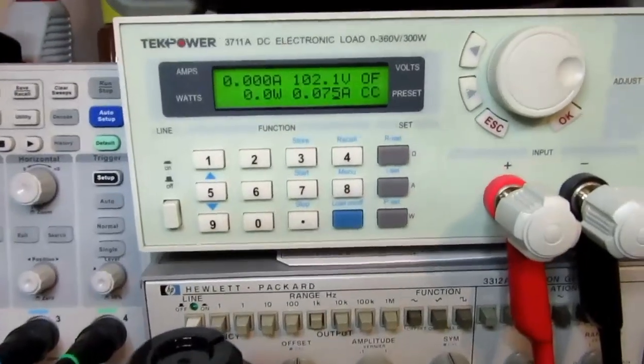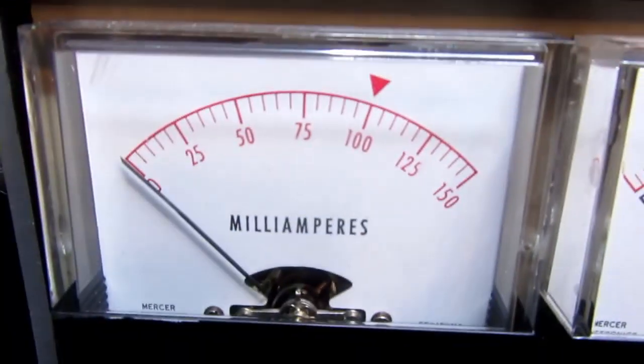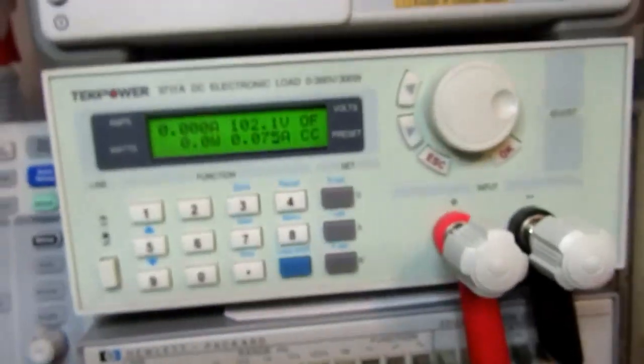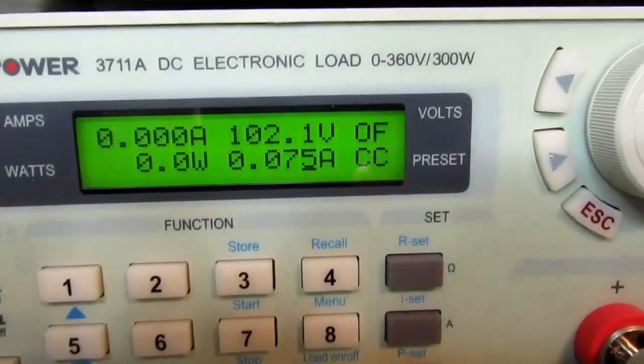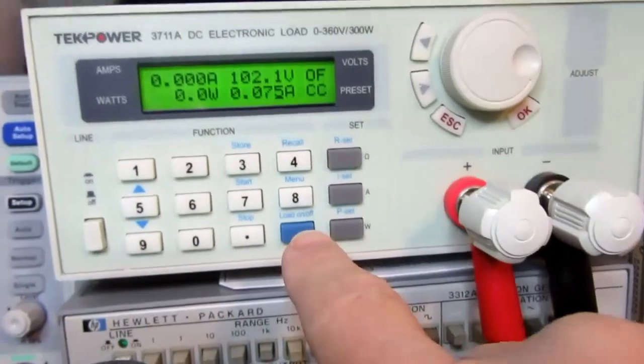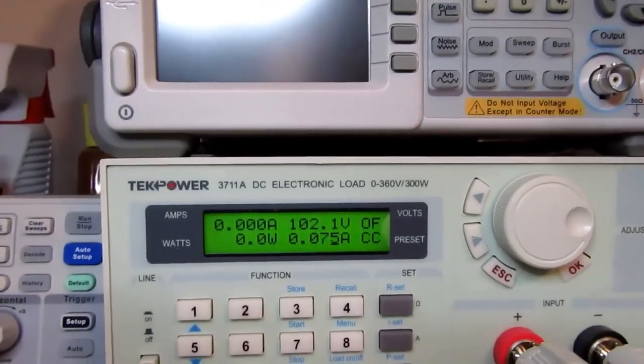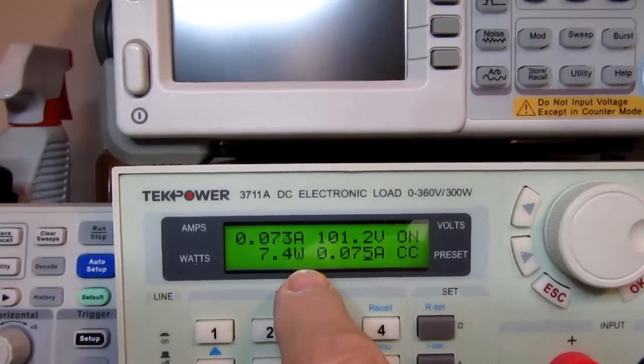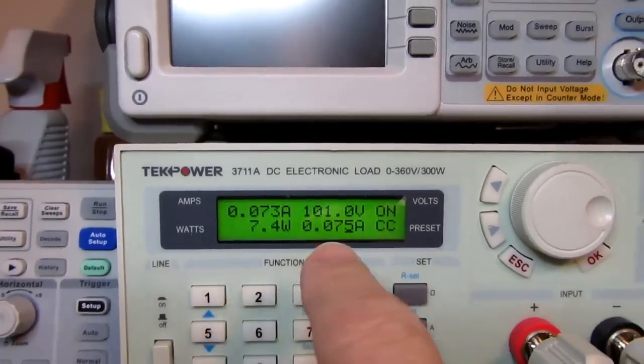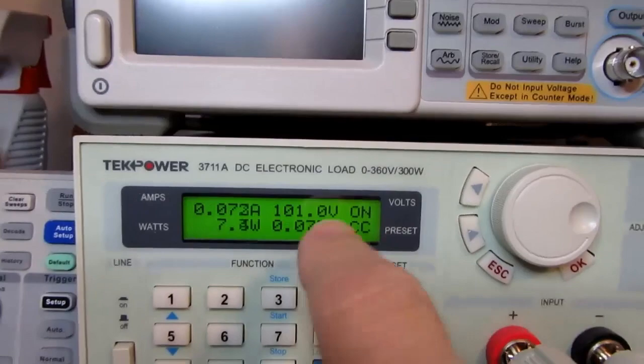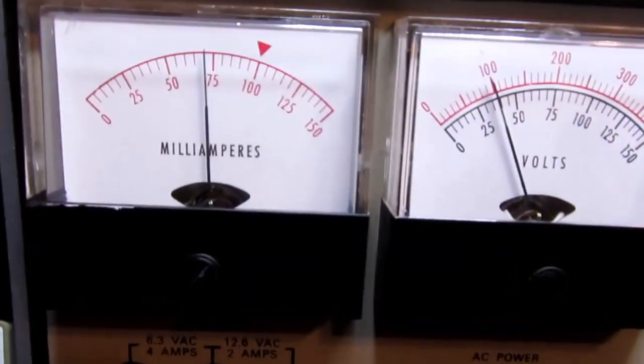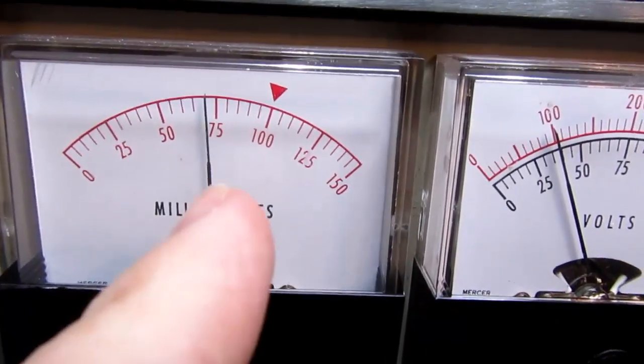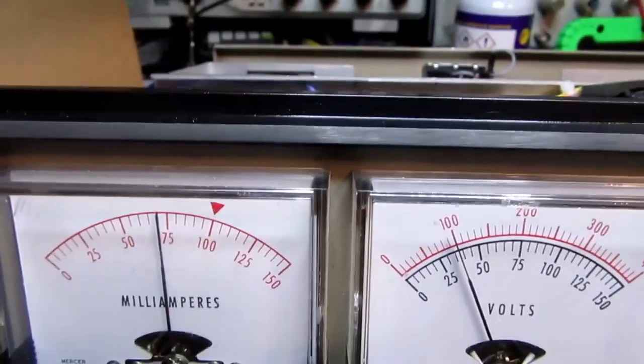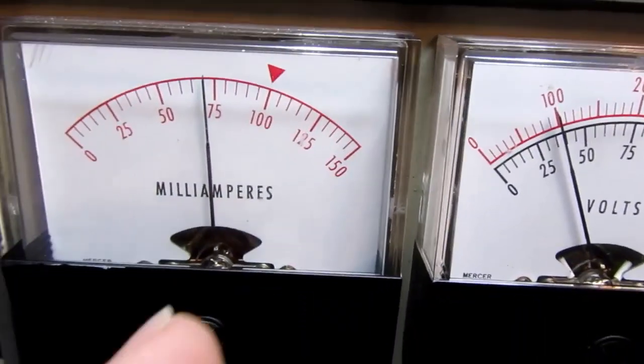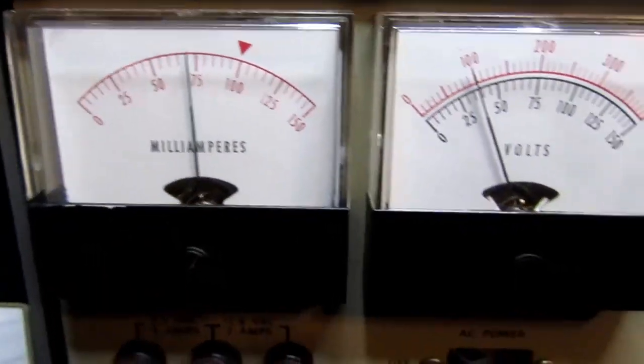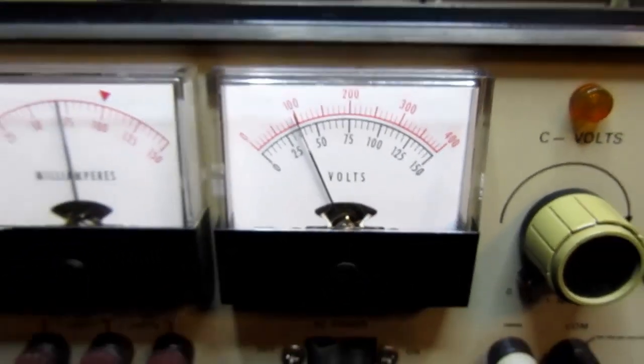Oh, I don't have the load actually engaged yet, which is why it's saying 0 down here. It is showing about 102 volts being applied, so I'm going to turn the load on. And now we see that the load here shows that we are pulling about 75 milliamps, and we're still at 100 volts. And the meter is showing pretty close to 75 milliamps. And we are more like 73 milliamps, so it is a little low. This isn't too inaccurate. And the voltage has not sagged.